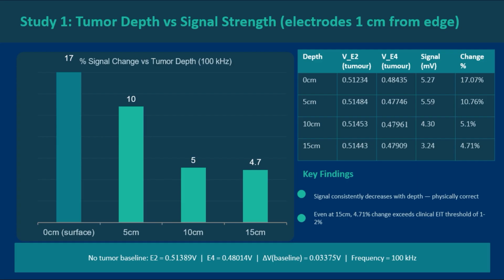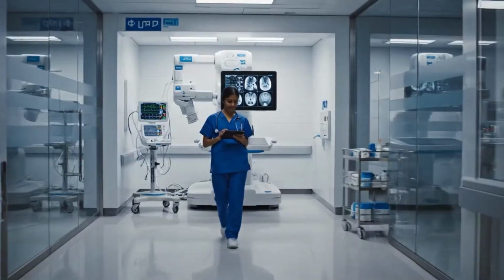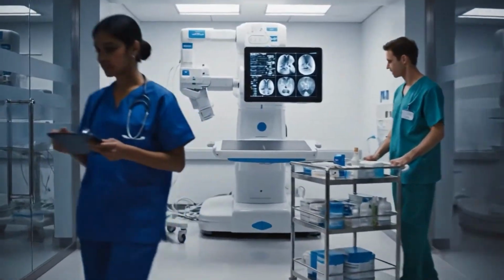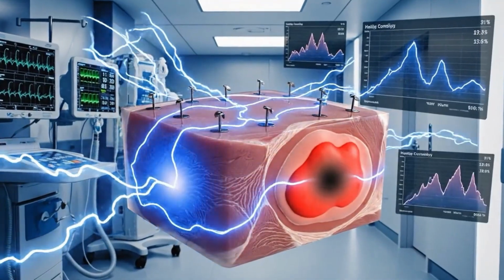We swept tumor depth from the surface to 15 centimeters. Signal change decreases with depth, as expected, about 17% at the surface, 10% at 5 centimeters, 5% at 10 centimeters, and nearly 4% at 15 centimeters. Crucially, every measurement exceeds the 1 to 2% EIT clinical detection threshold. This probe maintains sensitivity across the full clinically relevant breast tissue depth range.